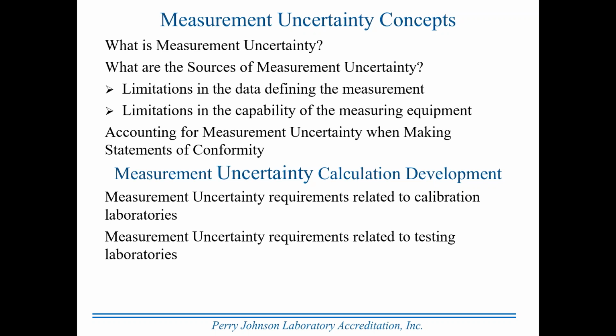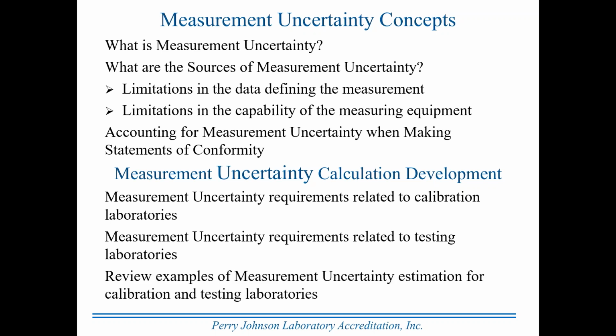Bear in mind, again, they're different. Calibration is always treated in a particular way with respect to estimating uncertainty. The contributors may be different, there may be more or less of them, but the manner in which uncertainty is estimated is consistent, and it is required for every calibration performed. Measurement uncertainty requirements related to testing laboratories, some of them will look identical to those for a calibration laboratory, and they will be. Some, it will not even be necessary to perform the estimate because the development of the method included in the acceptance criteria the uncertainty of results. We'll talk about that a little bit later as well. We'll review examples of measurement uncertainty estimation for calibration and testing laboratories.